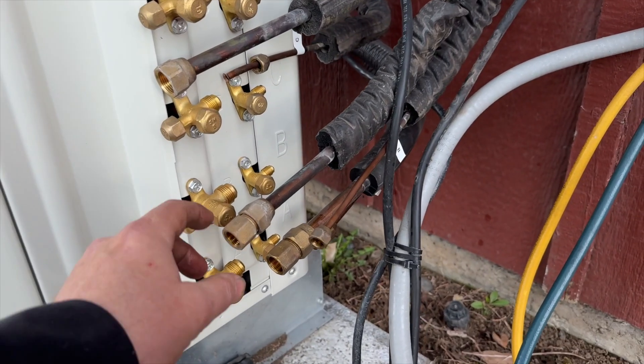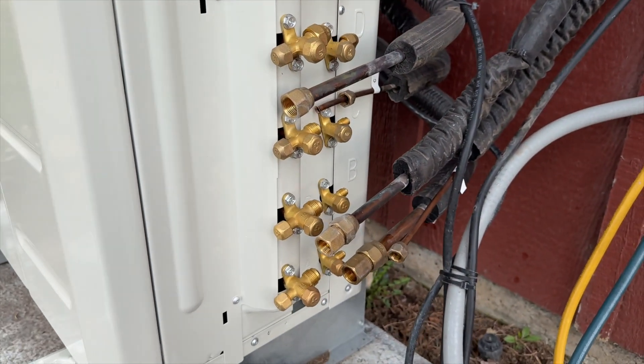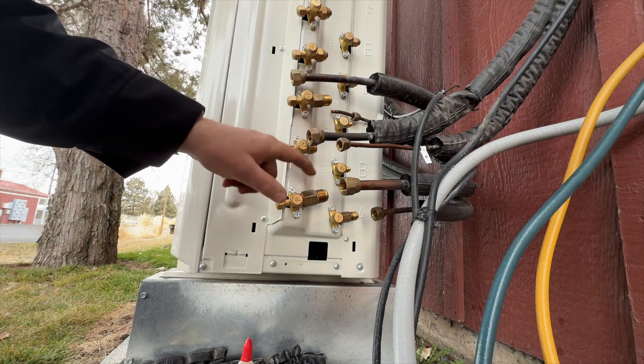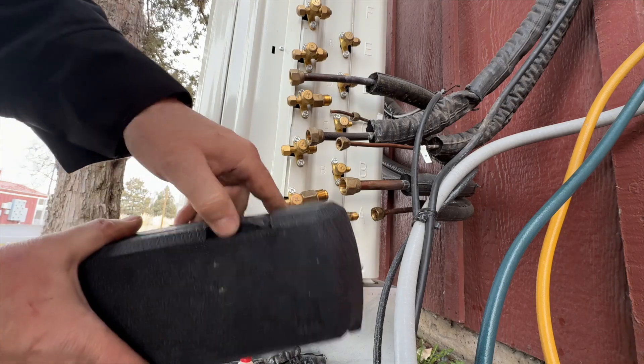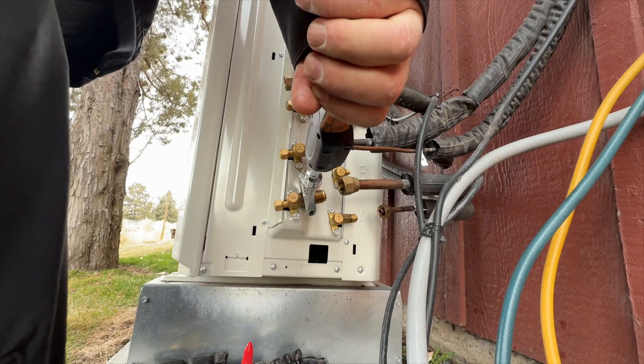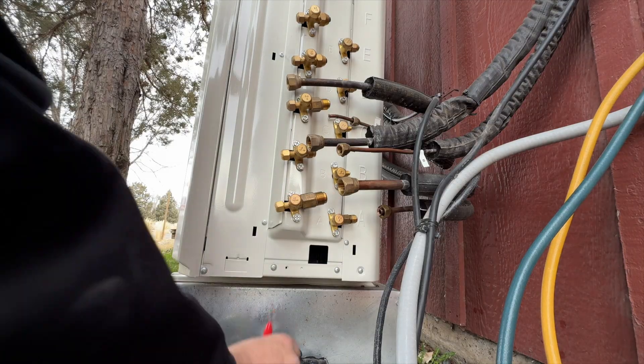Normally I would cut these off and re-flare them, but these flares are actually pretty good — I'm not seeing any burring or anything. They did a clean job, so I'm going to reuse them. We've got all our adapters put on. Now we need to torque these down: the 5/8-inch gets 65 newton-meters and the half-inch gets 56 newton-meters. I'm using my NAVAC torque wrench. Put some Nylog on there — you can see I'm putting it on the face right here, not on the threads, because that's where the sealing point is.